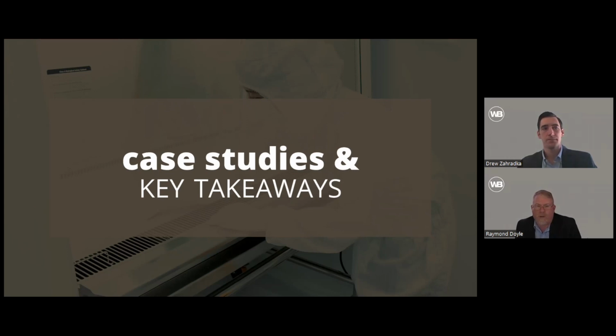We want to make sure that we're taking a more energy conscious approach, more of a performance approach, and look towards being able to use something like an active monitor, with regular monitoring of bacteria and particle count, so that we have the ability to reduce the energy used. You can always go back to the prescriptive method, but I think the performance method is going to drive a lot of the newer clean rooms in the market as the newer environments get built. Yep. And another solution could be, can that science be done in an isolator? Then you can have your background be under the isolator, and the room background can be one grade up or one classification less to help minimize the bigger impact of energy at the air handling unit level.